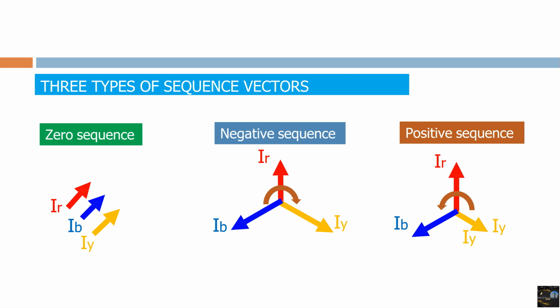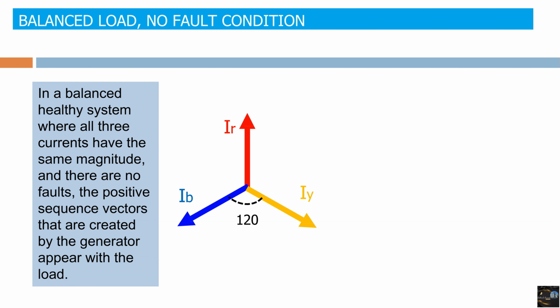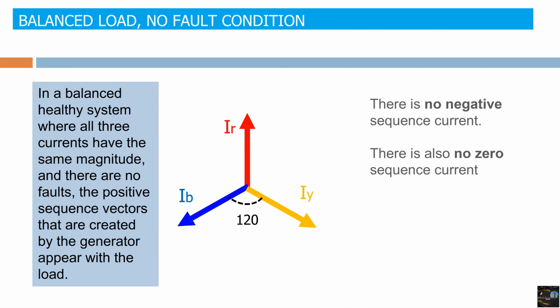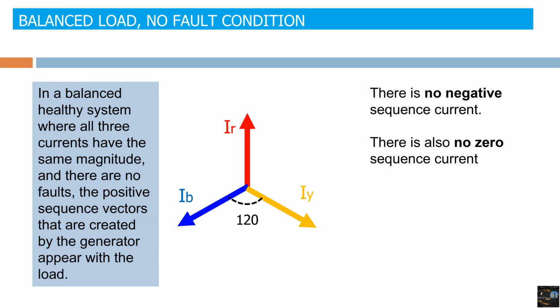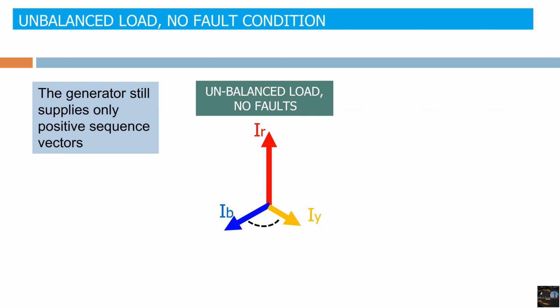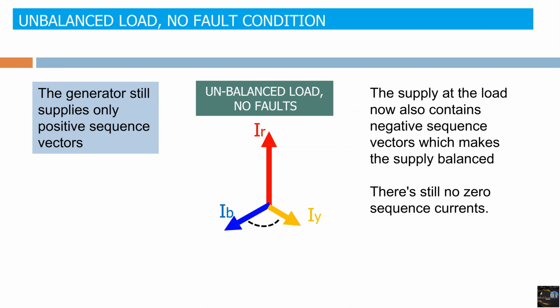First, we have a balanced load with no fault condition. In a balanced, healthy system where all three currents have the same magnitude and there is no fault, the positive sequence vectors that are created by the generator appear with the load. There are no negative sequence vectors and there are also no zero sequence vectors. Next we have unbalanced loads with no fault condition. In an unbalanced healthy system where the three-phase currents have different magnitudes and there are no ground faults, the generator still supplies only positive sequence vectors. The supply at the load now also contains negative sequence vectors, which makes the supply unbalanced. There are still no zero sequence currents.